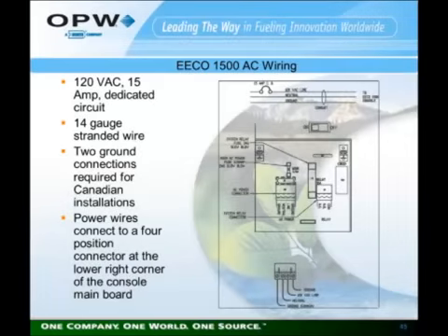The EECO 1500 AC wiring. On the main board in the lower right-hand corner is the AC power input connector. We have a 120 volt AC 15 amp dedicated circuit requirement, 14 gauge stranded wire minimum. You'll notice that it is a 4-terminal connector with 2 ground connections. Those are required for Canada and some other countries. The board is screened with labels for each terminal so that you know which terminal should receive which wire.